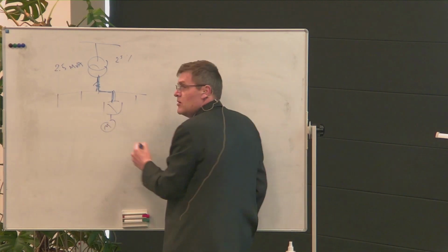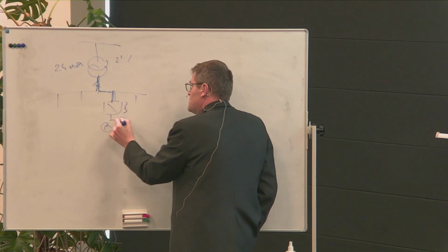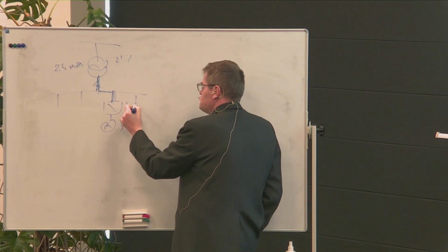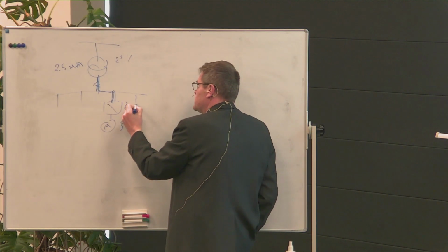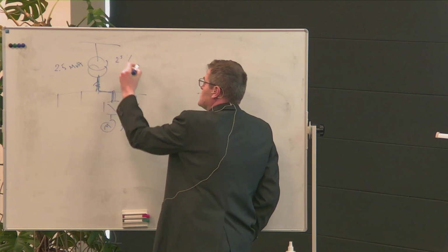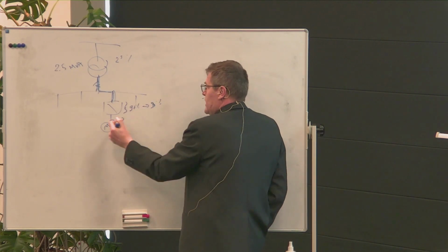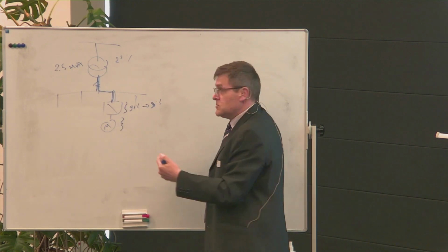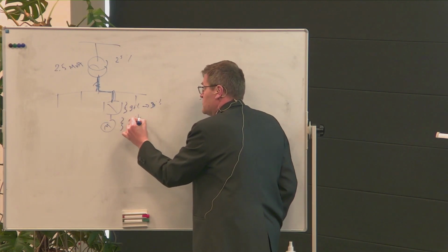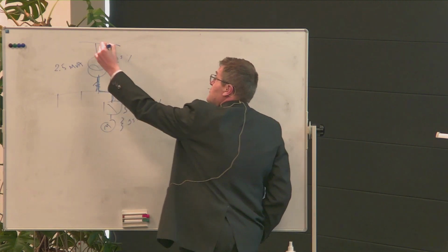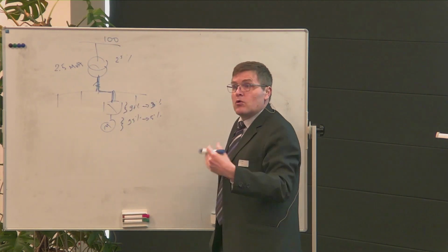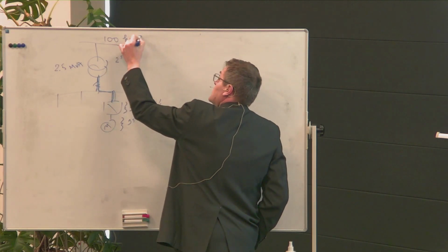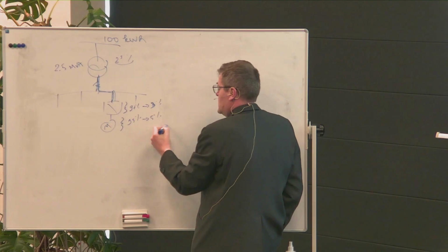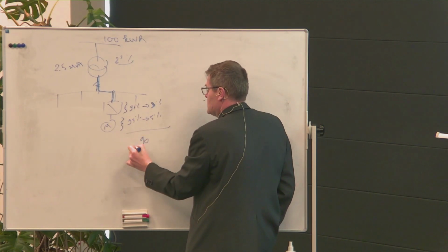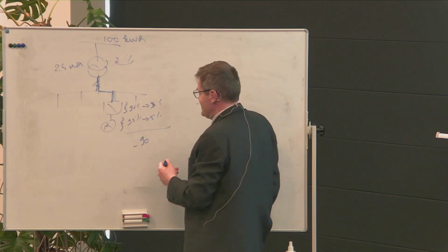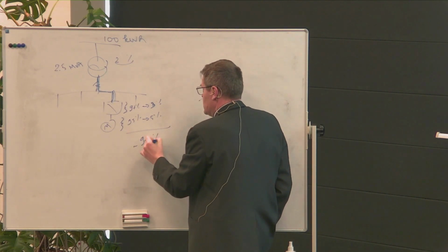And you have, I would say, a lot of motors. Let's say that the variable speed drive plus the motor efficiency, as announced in the data sheet, you can see that it is 97% efficiency. So here, losses are 3%. And in the motor itself, you also have some losses. We announced 95% efficiency, so 5%. So that means that if you have 100 kilowatt hours of energy, here you have minus 2.5. You have 90-ish. I will take 2% just to make it simple. So you have an efficiency of 90%.